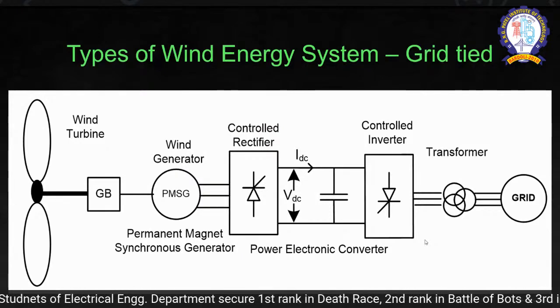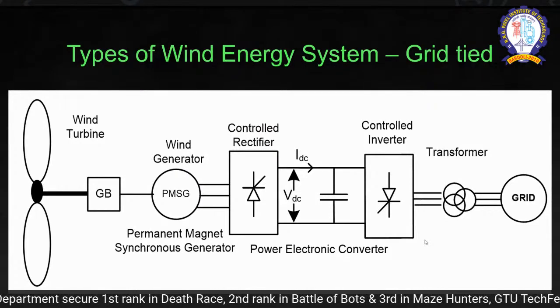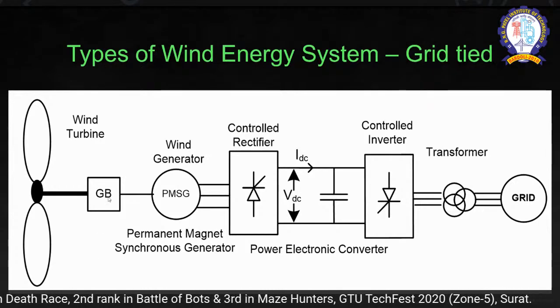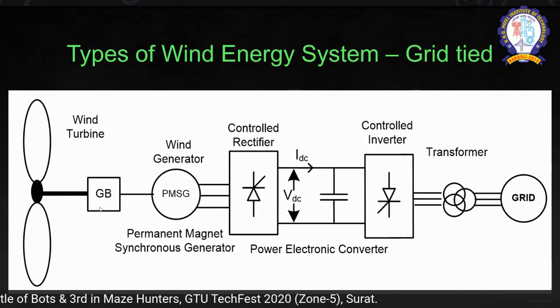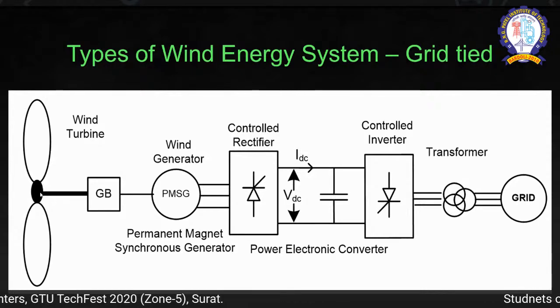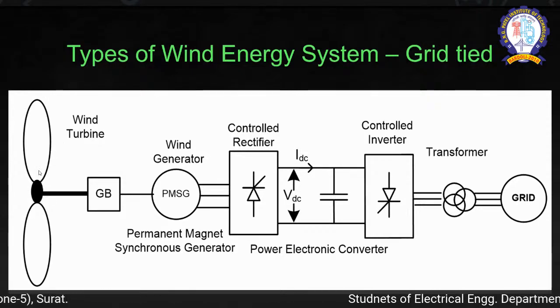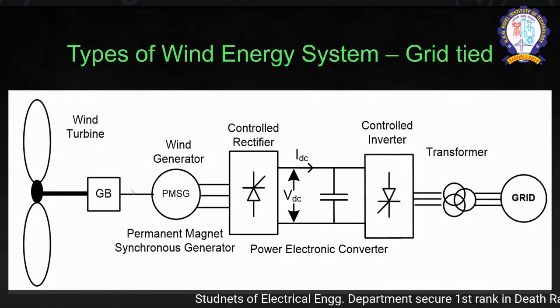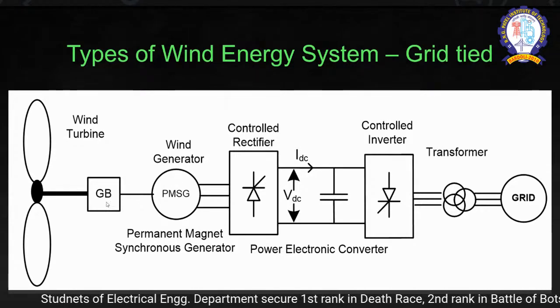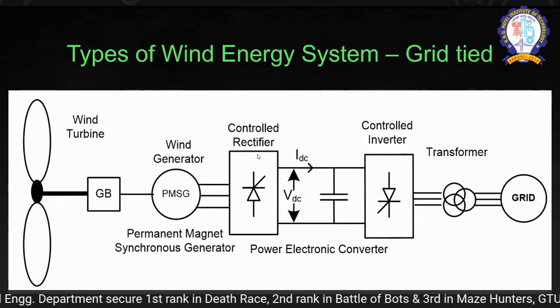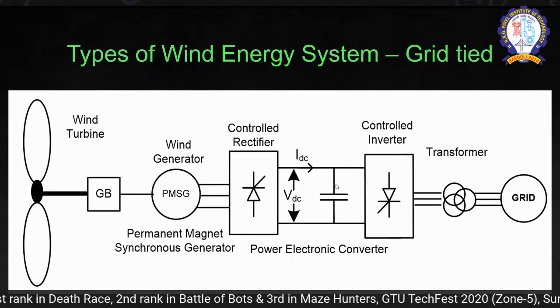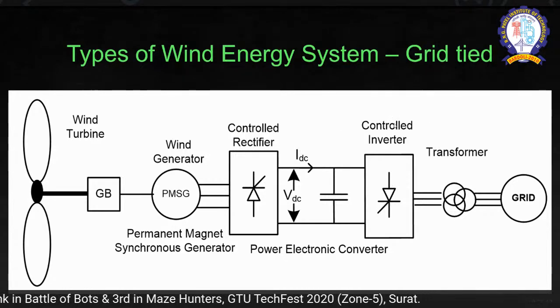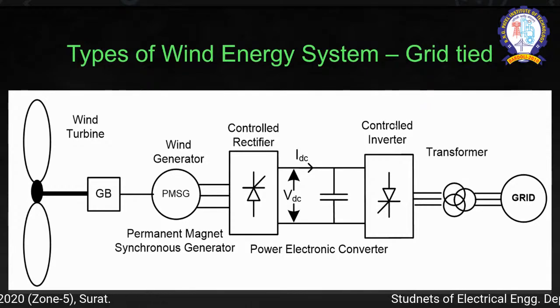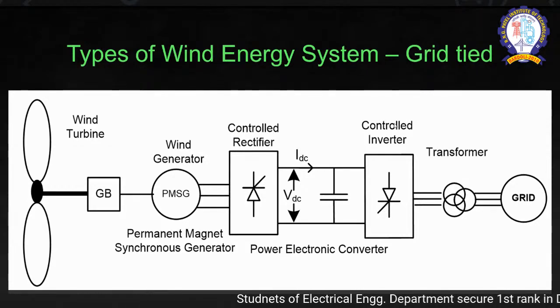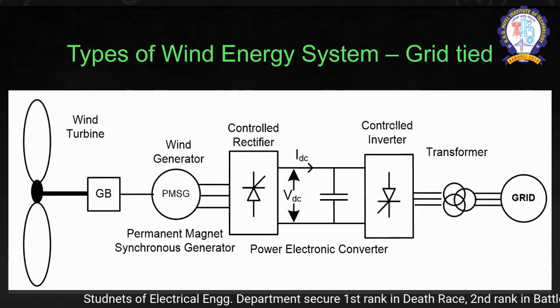This is the block diagram of the direct drive system. It is known as the type D system. The gearbox in this case is optional. So if you remove the gearbox over here, this turbine and this generator will become direct drive. Then we have the controlled rectifier, then the DC link capacitor, then the controlled inverter, and then the transformer. So in the transformer, we have certain aspects of various components of the windmill system.